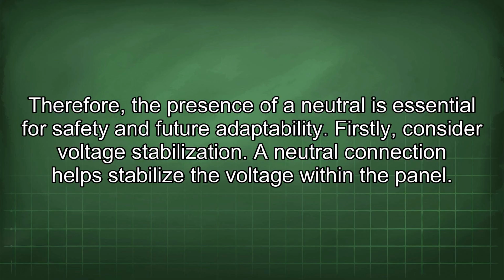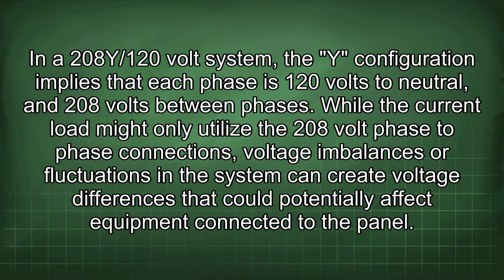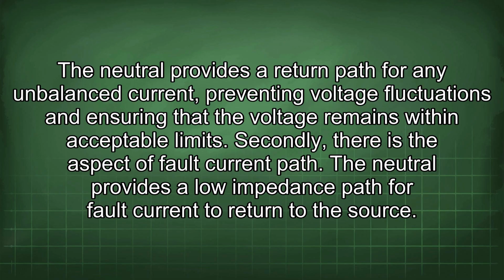Firstly, consider voltage stabilization. A neutral connection helps stabilize the voltage within the panel. In a 208Y/120 volt system, the Y configuration implies that each phase is 120 volts to neutral and 208 volts between phases. While the current load might only utilize the 208 volt phase-to-phase connections, voltage imbalances or fluctuations in the system can create voltage differences that could potentially affect equipment connected to the panel.